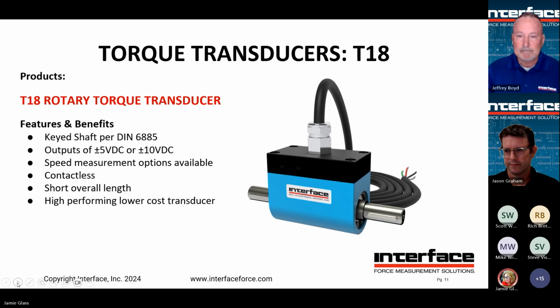Next slide, please. Rotary torque. So kind of getting away from force measurement here and talking a little bit about torque. This one is a rotating torque sensor, so we can measure dynamic torques. Some of the advantages here: high level analog output, plus or minus 5 volt, or plus or minus 10 volt. Keyed shafts is a feature that can be integrated into the T18. High performance, non-contact signal transmission, so not any wearing brushes or slip rings, that sort of thing.